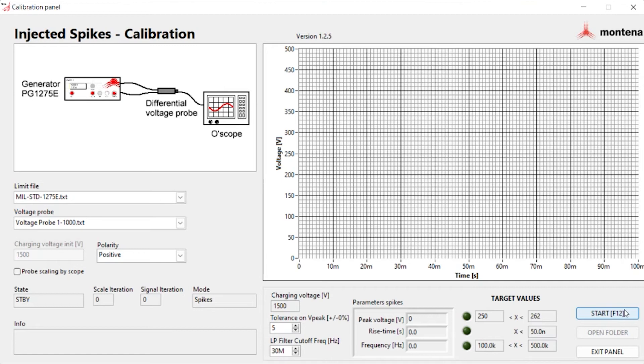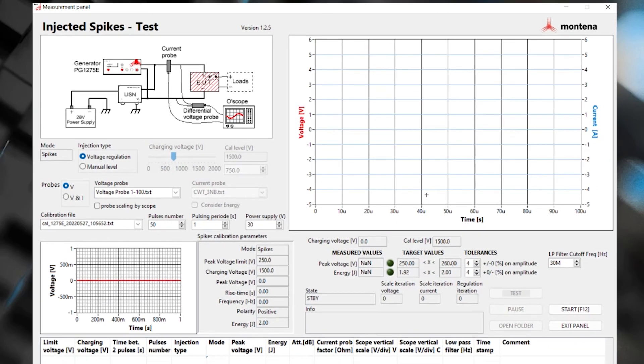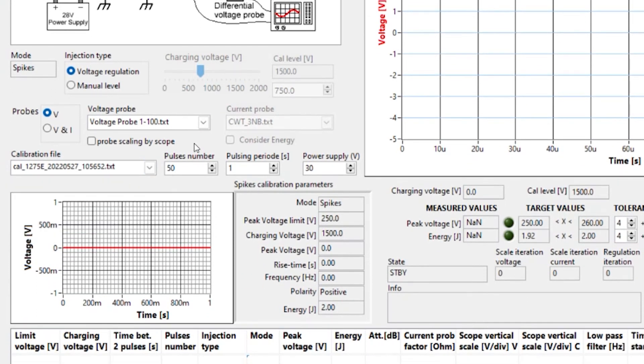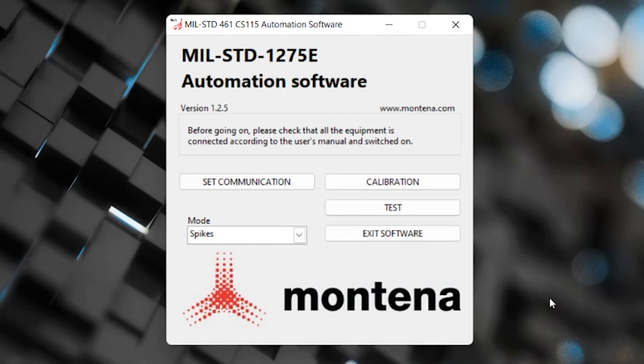The calibration communicates with the transient generator using your oscilloscope data to drive a waveform on screen. We don't actually have it hooked up right now, so let's exit this panel. Let's take a look at the test option. This is the injected spikes test, indicated in the top left corner. Below that you'll see the setup configuration with the current monitoring probe and differential voltage probe, along with a power supply and load. You can select injection type, probes, and voltage regulation. You'll also see calibration file name, number of pulses, pulsing period, and power supply settings. When you're ready to run the test, hit start F12.